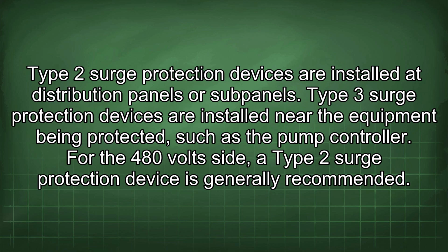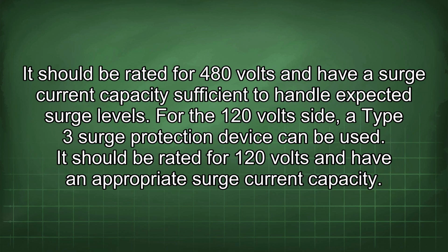Type 3 surge protection devices are installed near the equipment being protected, such as the pump controller. For the 480 volt side, a Type 2 surge protection device is generally recommended. It should be rated for 480 volts and have a surge current capacity sufficient to handle expected surge levels. For the 120 volt side, a Type 3 surge protection device can be used. It should be rated for 120 volts and have an appropriate surge current capacity.